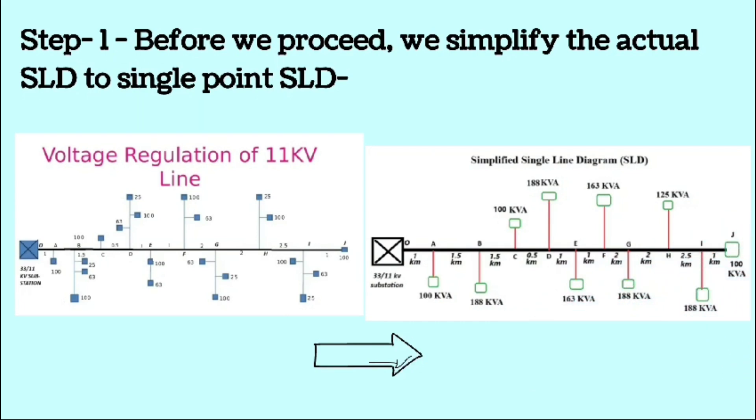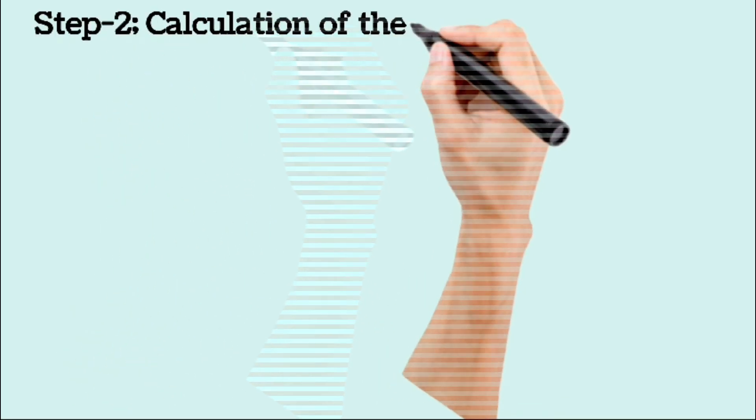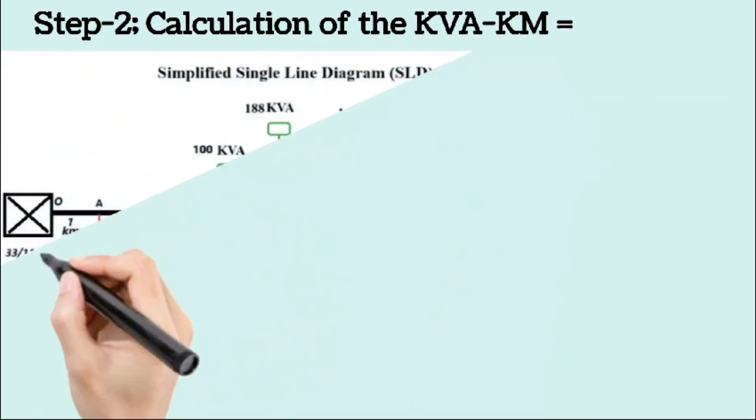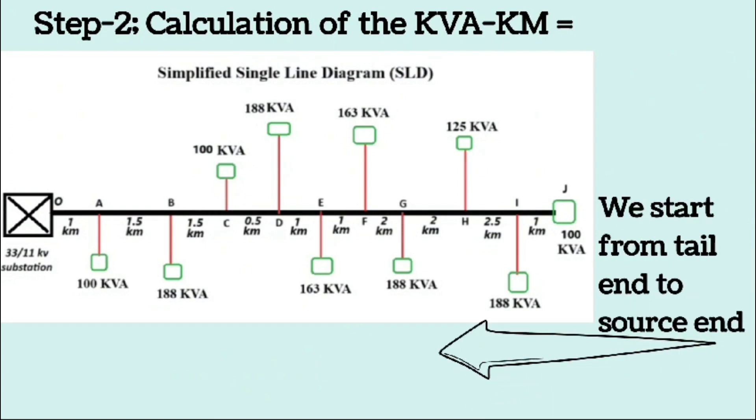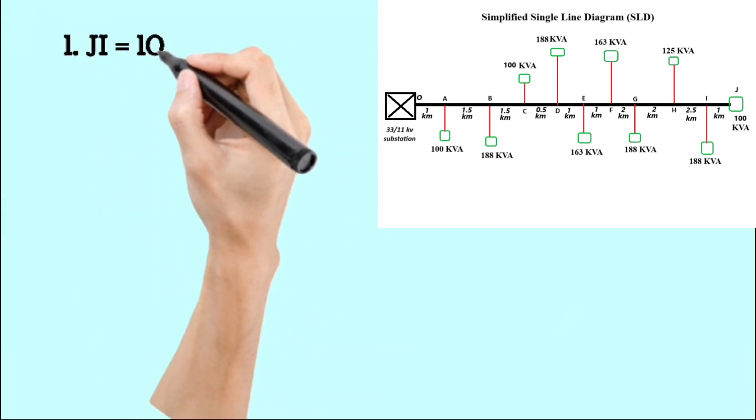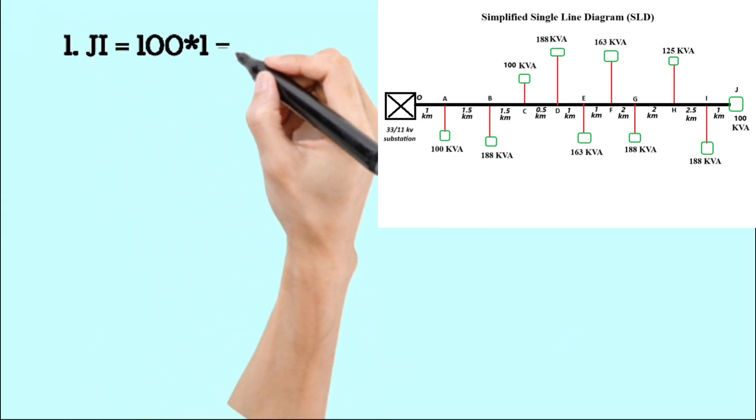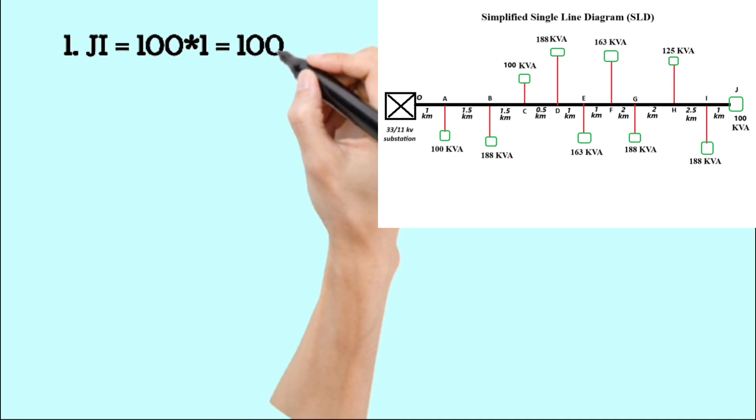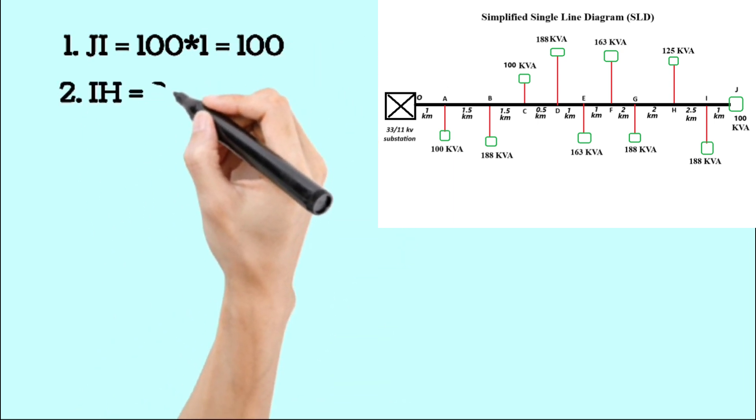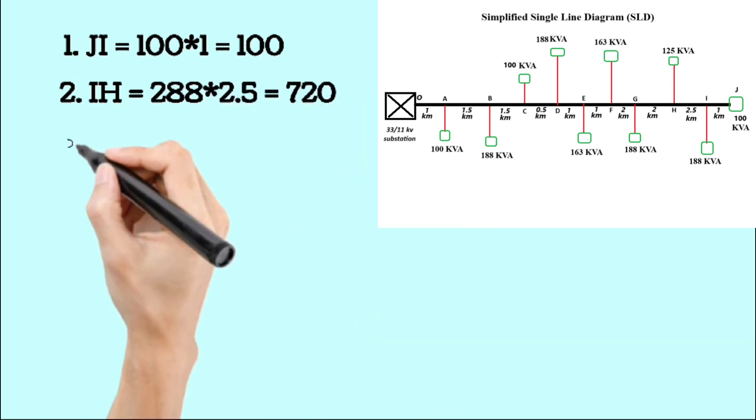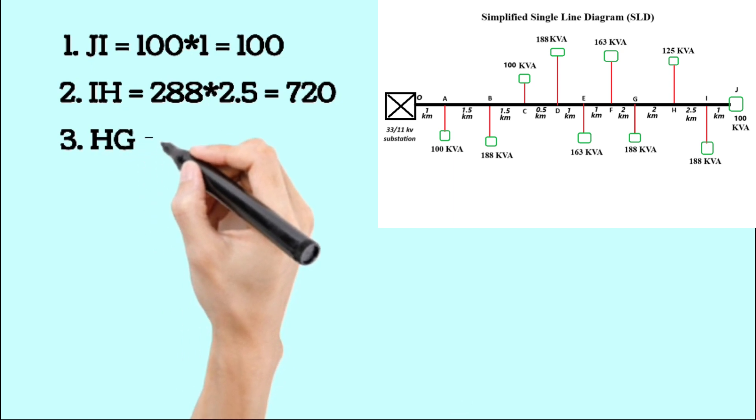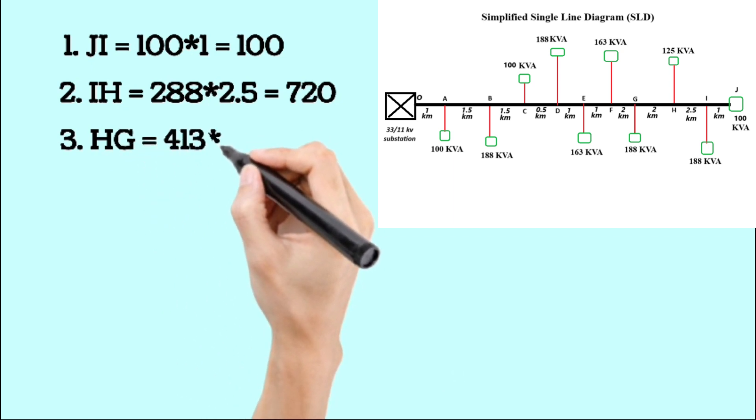Now in step one, we calculate the kVA kilometer from the single line diagram, and this we will calculate from tail end to source end. Let's calculate the total kVA kilometers step by step from tail end to source end. For segment JI: 100 multiplied by 1 equals 100. For segment IH: 288 multiplied by 2.5 equals 720. For segment HG: 413 multiplied by 2 equals 826. For segment GF: 601 multiplied by 2 equals 1202.